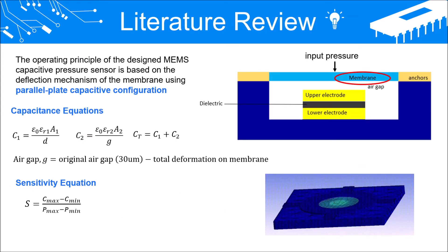The operating principle of the sensor is based on the deflection mechanism of the membrane using parallel plate capacitive configuration. As the input pressure is exerted, membrane deflection will lead to the subsequent change in air gap, capacitance, and sensitivity. C1 here is the capacitance between the upper and lower electrodes, whereas C2 is the capacitance between the upper electrode and membrane, and Ct is the total capacitance of the sensor, which is the summation of C1 and C2. Membrane deflection affecting the air gap will bring changes to C2. Sensitivity is defined as the ability to sense the difference in capacitance upon difference in pressure.